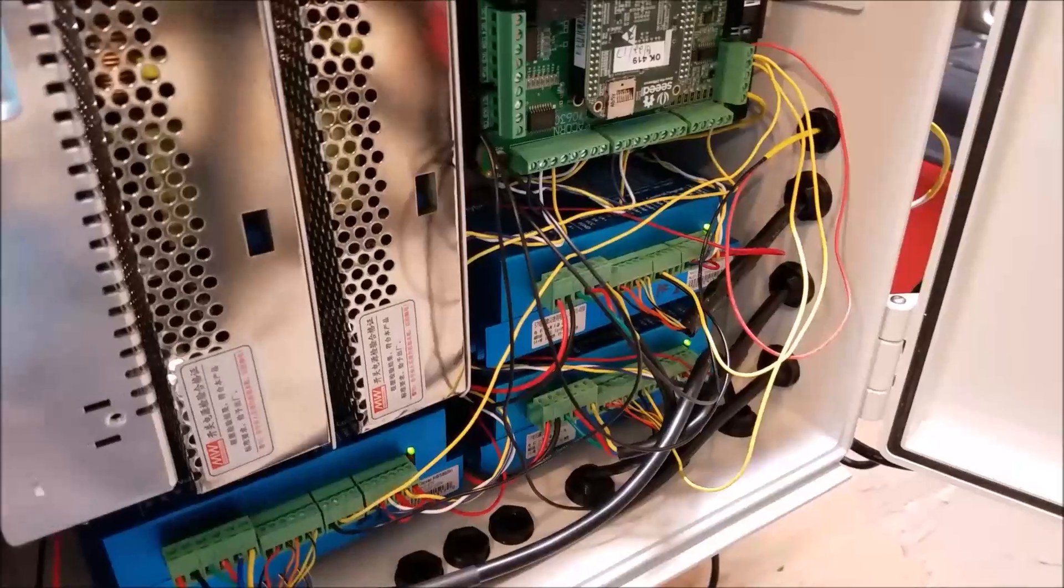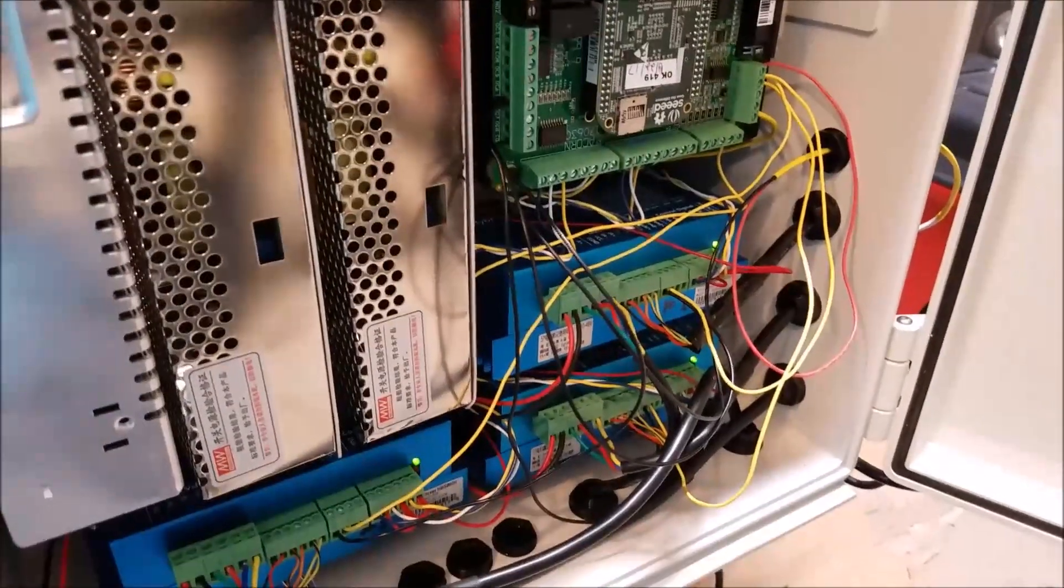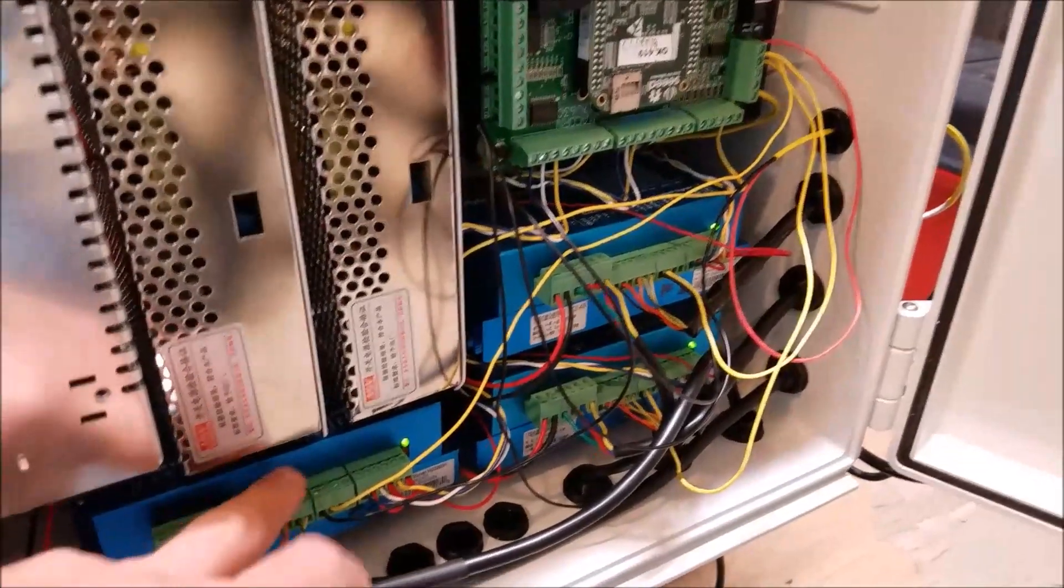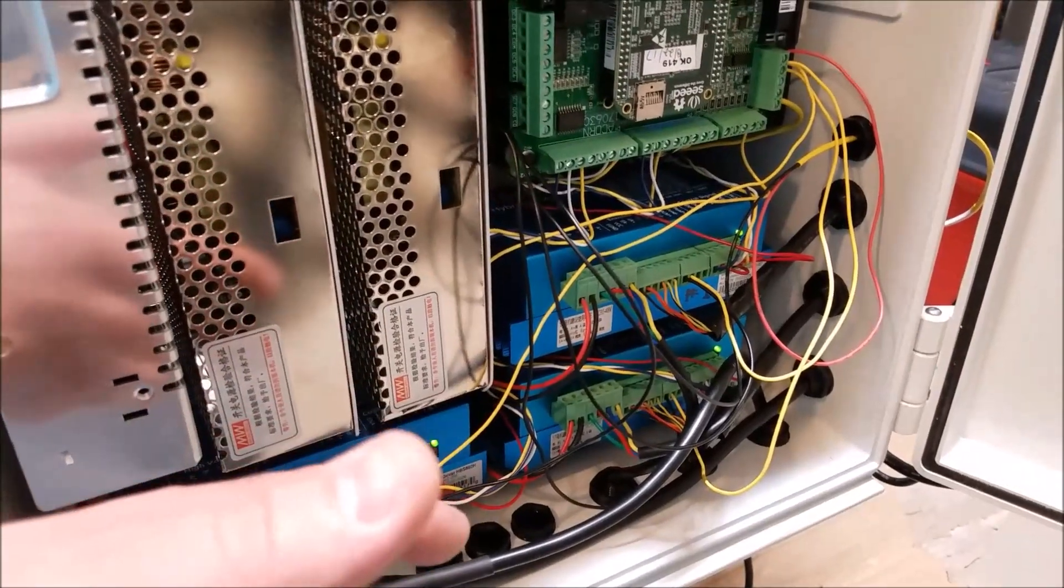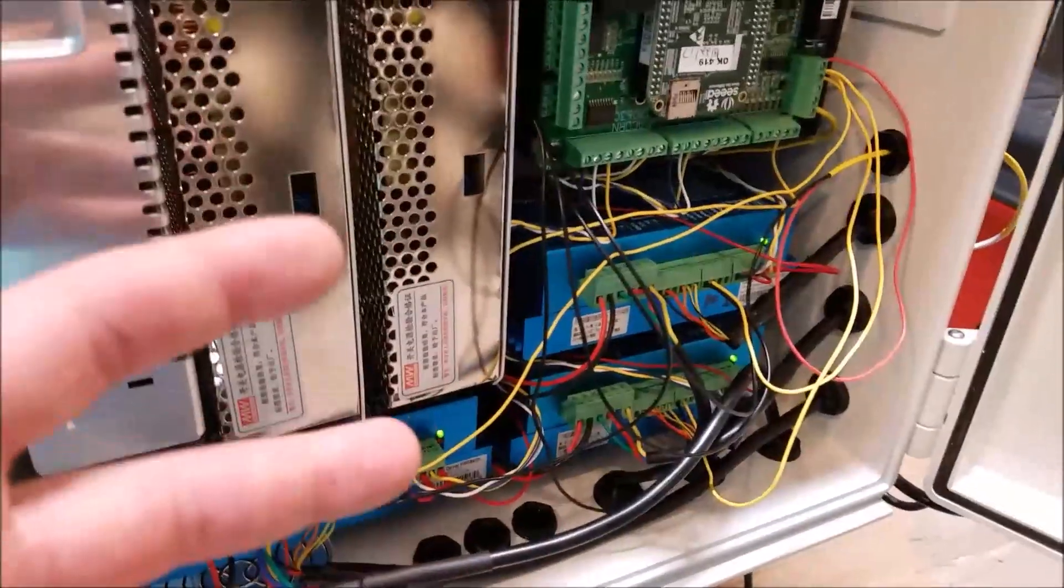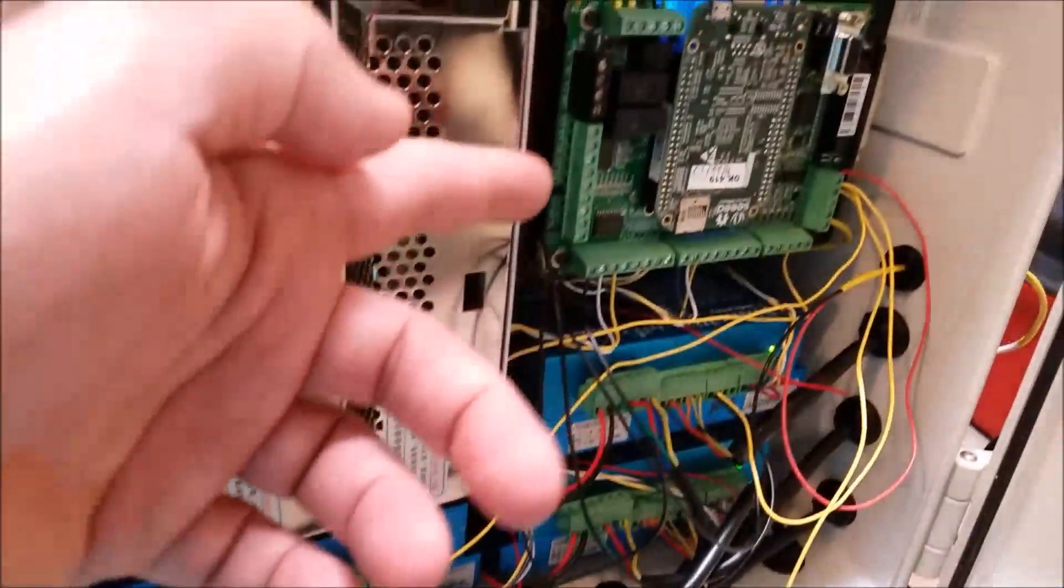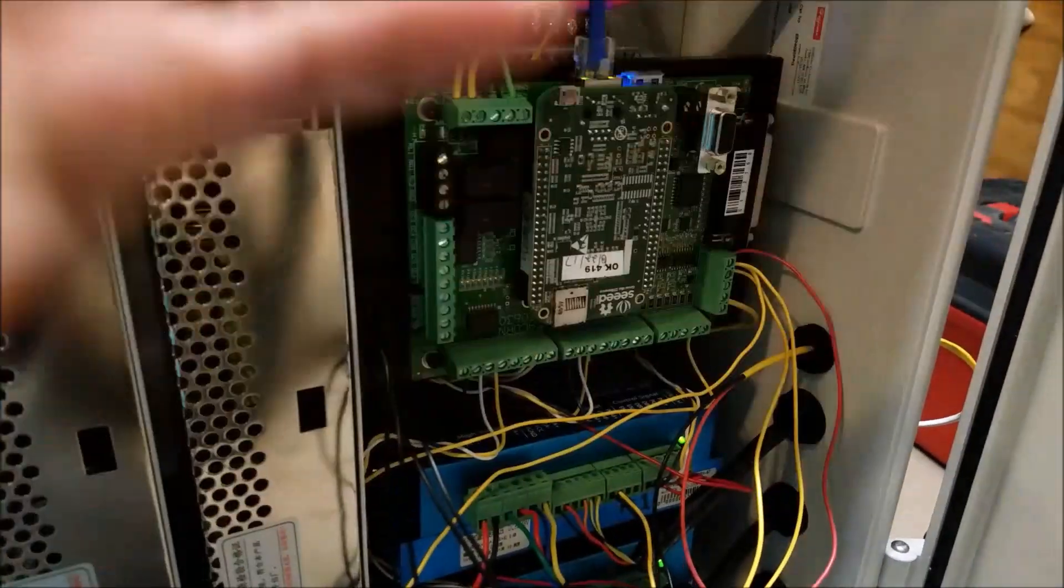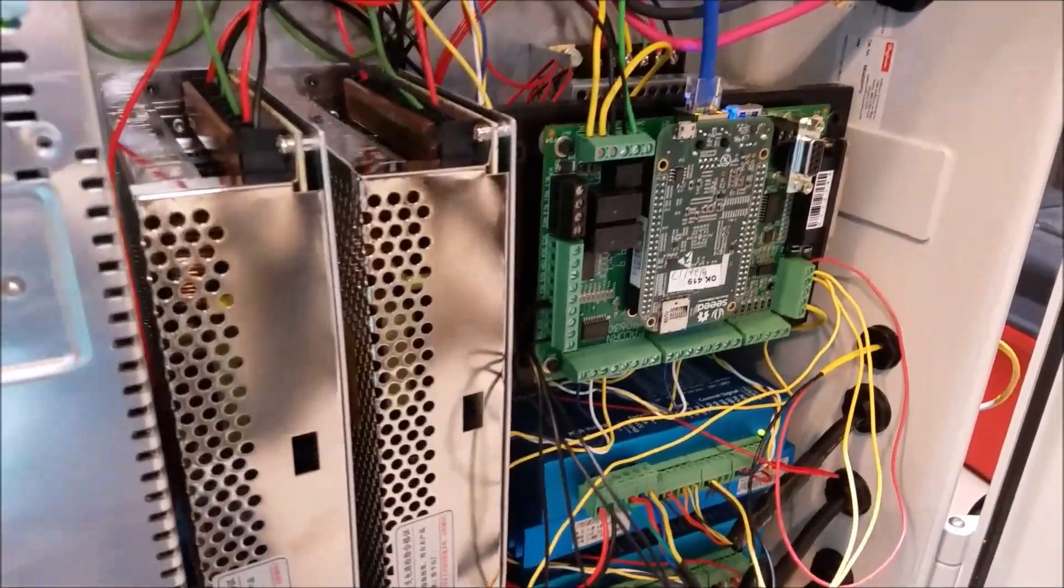So basically I just have all these things wired in parallel. So if any one of these, I like to think of it as a switch. If the little switch inside of any of these drives, which is normally open when it's happy, if any of these drives alarm out, that switch will close and then it will trigger input number two and the software will bomb out.